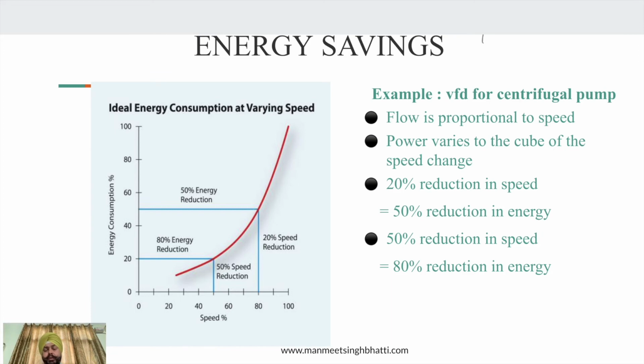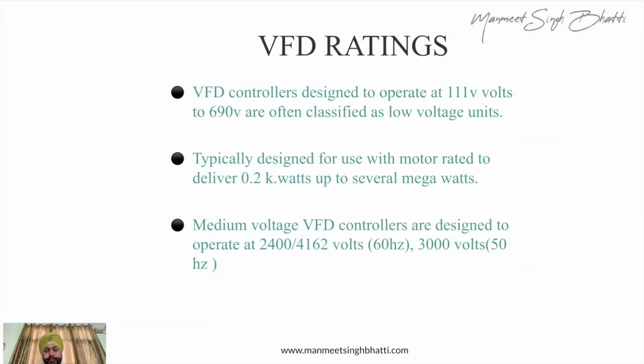We can help you find out a proper calculation based on the load factor, motor conditions and all those things also. But this is a tentative idea, because we already have the calculations done for this. It's a standard practice for most of the VFDs you will be getting. You may get 1%, 2%, 5% here and there, but most of the saving that you are going to get is in this same range. So this is the way the energy saving is achieved by putting in a VFD.